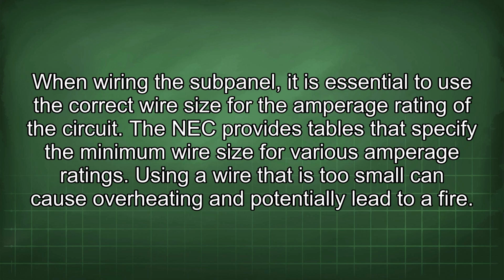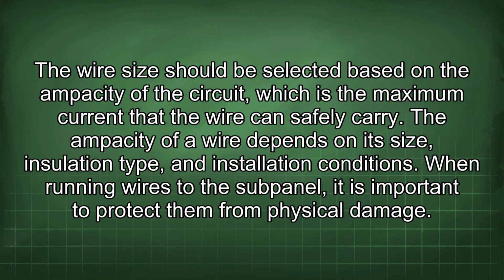When wiring the subpanel, it is essential to use the correct wire size for the amperage rating of the circuit. The NEC provides tables that specify the minimum wire size for various amperage ratings. Using a wire that is too small can cause overheating and potentially lead to a fire. The wire size should be selected based on the ampacity of the circuit, which is the maximum current that the wire can safely carry. The ampacity of a wire depends on its size, insulation type, and installation conditions.